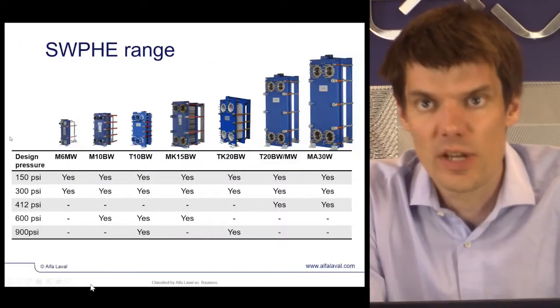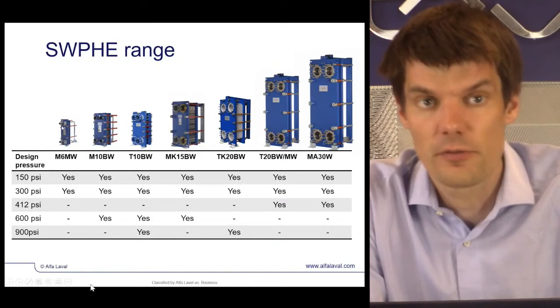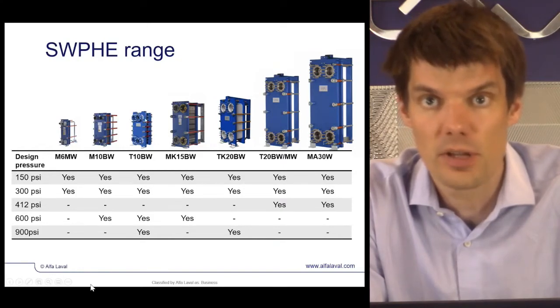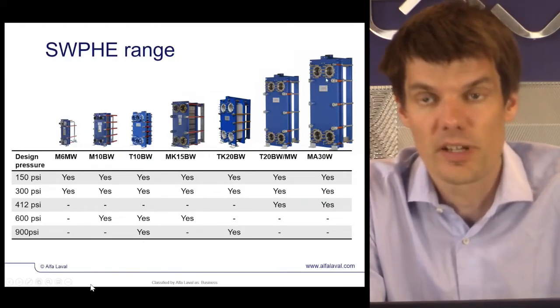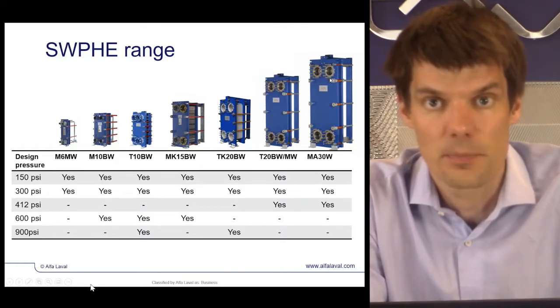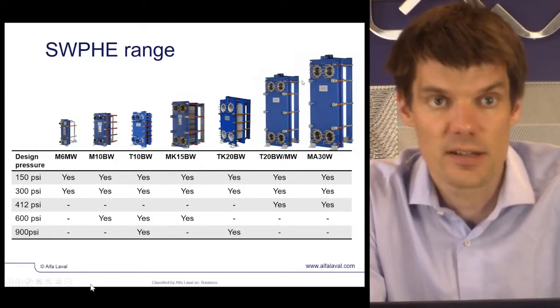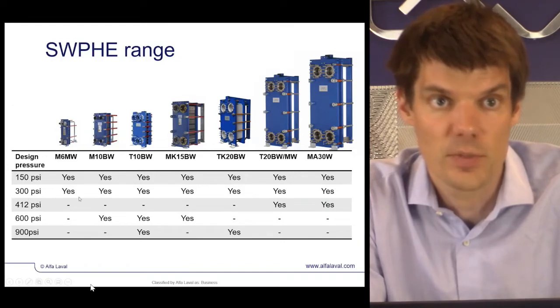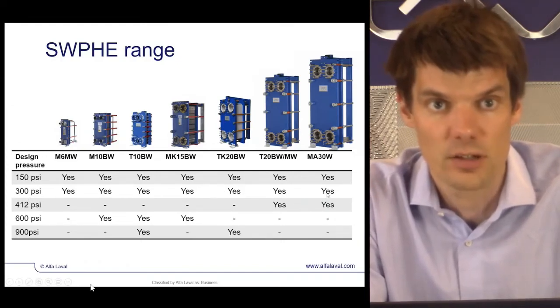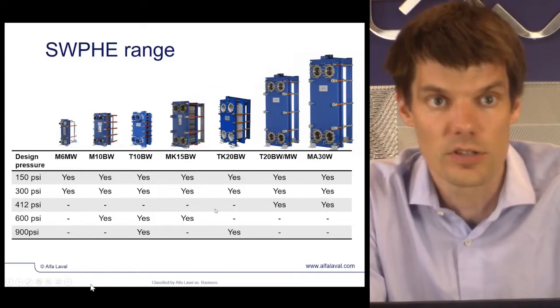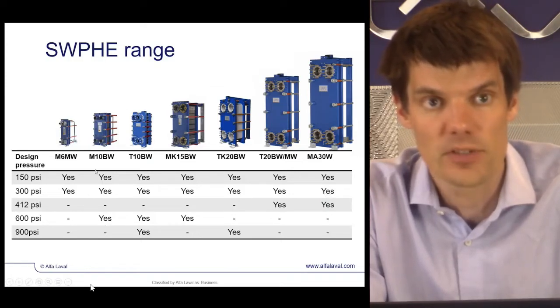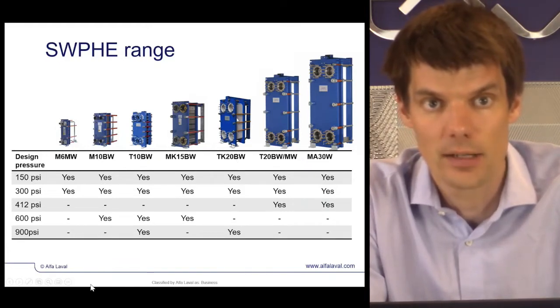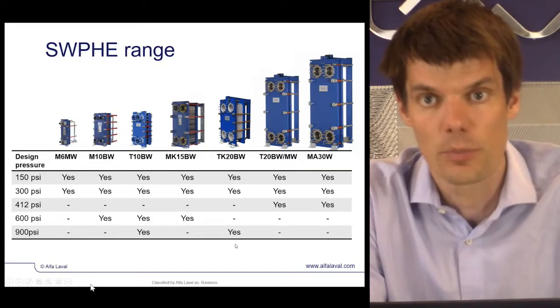Alfa Laval is offering a range of semi-welded plate heat exchangers starting from the 3-inch M6MW and going up to the quite big MA30W with the 12-inch connection. This makes it possible to find the right unit for the right application. Pressure-wise, the standard semi-welded plate heat exchanger comes with a 300 psi design pressure for evaporators and condensers, but there are also units available for 600 and 900 psi for CO2 and cascade and heat pump operations.